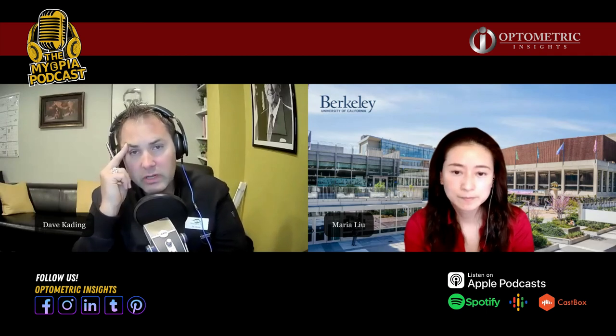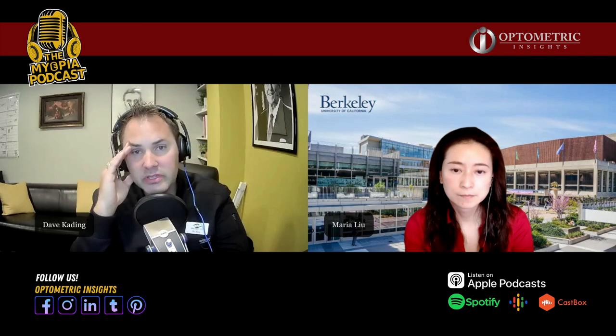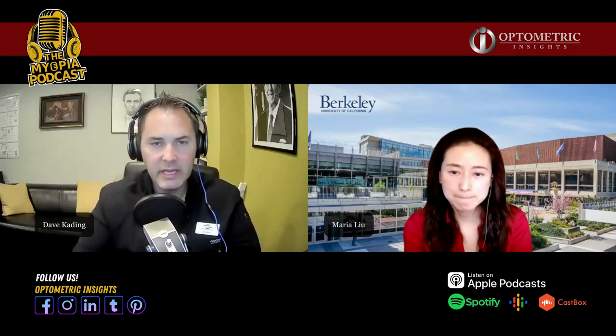That's also important as we look for biometers to become more readily available — instruments like the Lenstar, the Myopia Master. Angle kappa is also available in several corneal topographers. If you're looking at the pupil barycenter, it gives you a delta x and delta y — basically the vertical and horizontal distance of the pupil center relative to the optical axis of the instrument. And typically topographers have marks that indicate either the visual axis or pupil center.